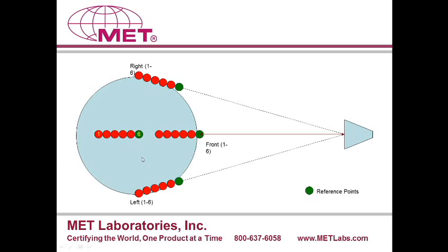How many heights does this process have to be repeated? It has to be done at 1 meter and at 1.5 meter for both polarizations — vertical and horizontal. The highest point where this measurement needs to be done will be based on the maximum size of the EUT you plan to test at your facility. If you are testing rack mount equipment which is 7 feet tall, and cables are about 1 foot above the rack height, then you would be better off going to 2.5 meters. But again, it really depends on what sort of EUTs a certain facility plans to test.